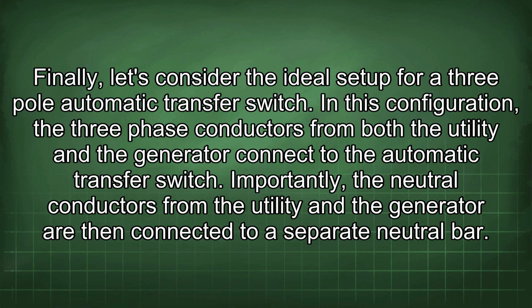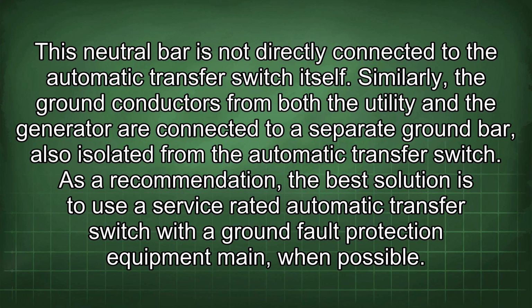Finally, let's consider the ideal setup for a 3-pole automatic transfer switch. In this configuration, the 3-phase conductors from both the utility and the generator connect to the automatic transfer switch. Importantly, the neutral conductors from the utility and the generator are then connected to a separate neutral bar. This neutral bar is not directly connected to the automatic transfer switch itself. Similarly, the ground conductors from both the utility and the generator are connected to a separate ground bar, also isolated from the automatic transfer switch.